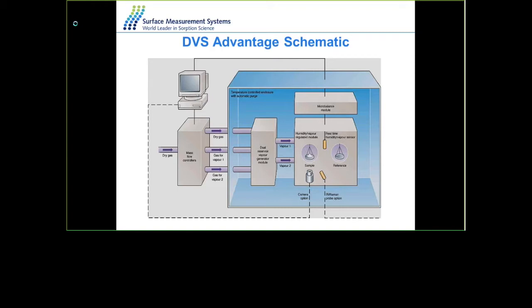Here is a schematic diagram of the system. Dry gas is introduced through a series of very accurate mass flow controllers. The dry gas bubbles through the water or vapor reservoir, generating saturated vapor which is then mixed with dry gas to generate the required target concentration. This is then introduced into the sample chamber and the reference pan chamber. A camera underneath the sample chamber can take images of the sample at different relative humidities or vapor concentrations.